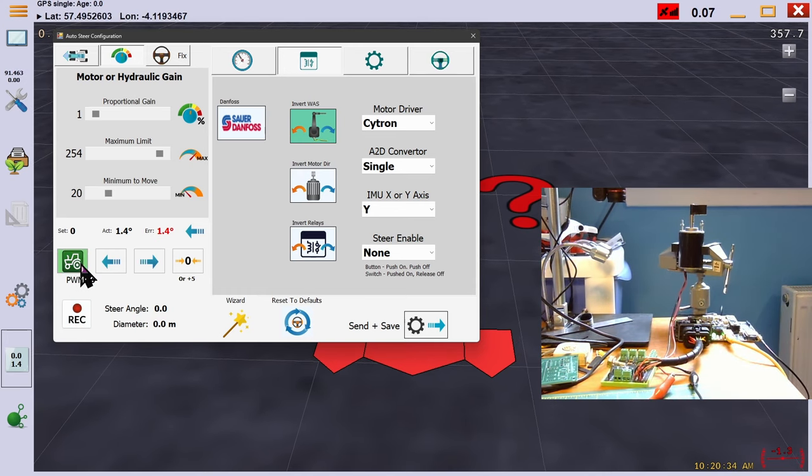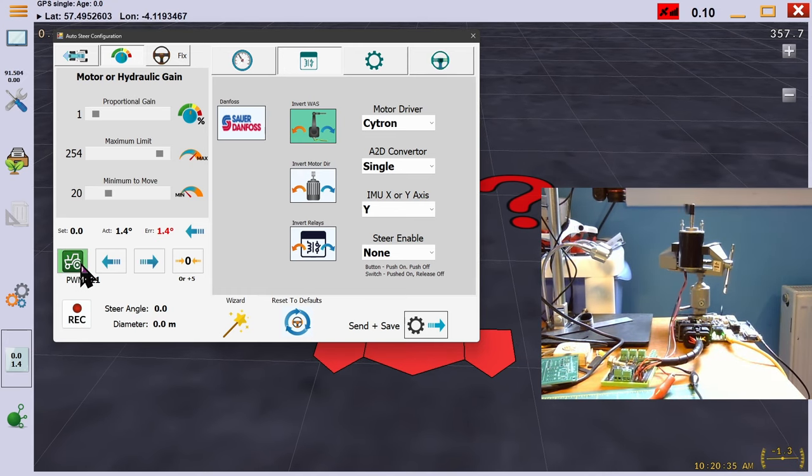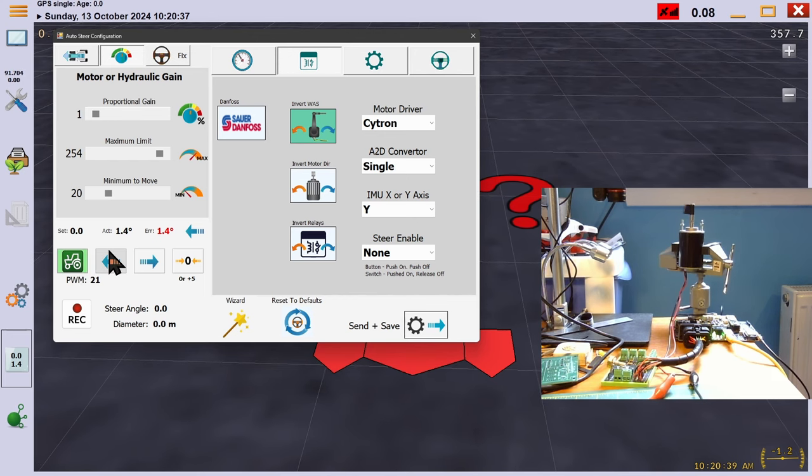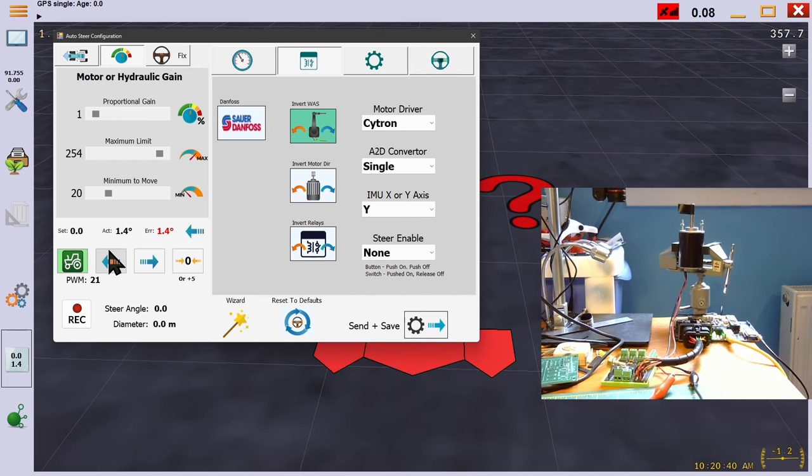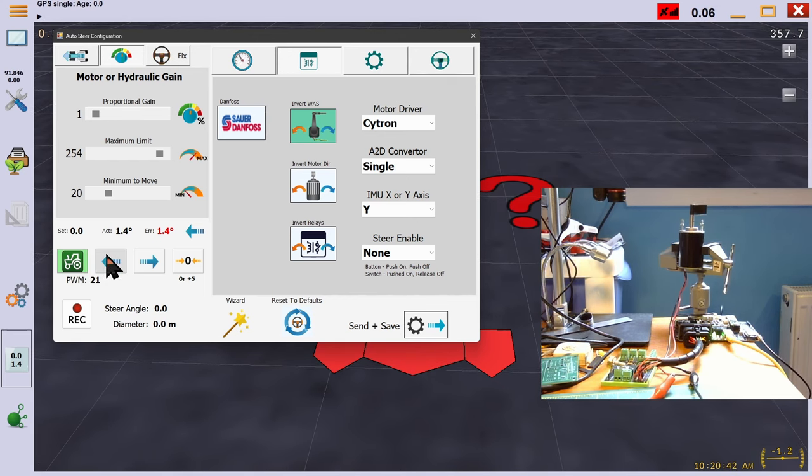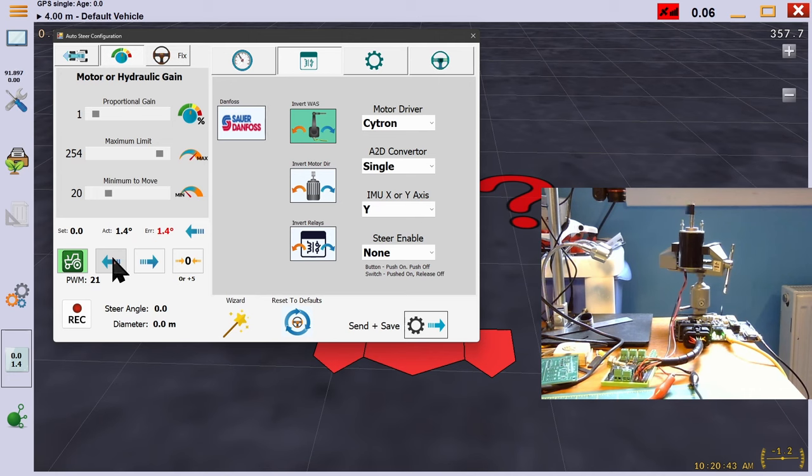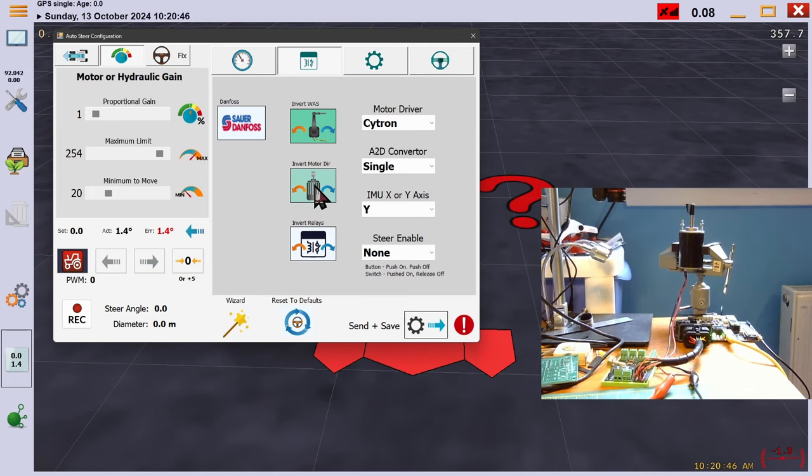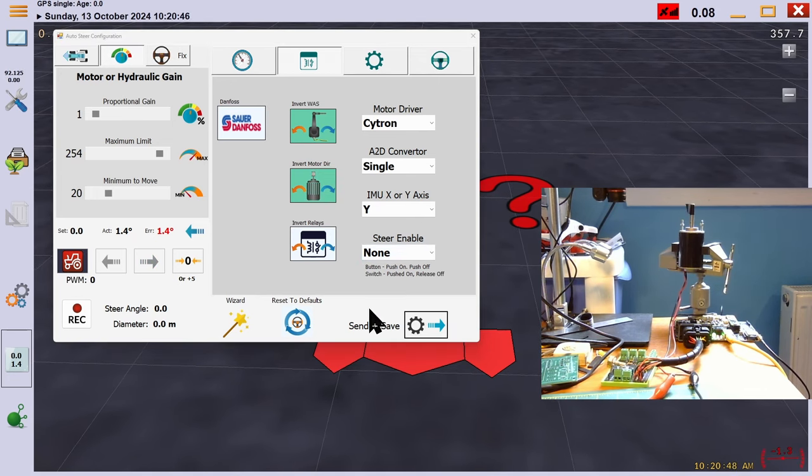Now, 1 times 1.4 is 1.4, plus 20 is showing 21. AOG rounds the display as shown so it's an integer. In my case, the wheel was turning in the wrong direction, so I inverted the motor direction, then send and save.